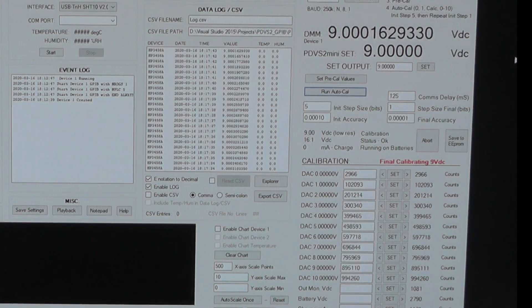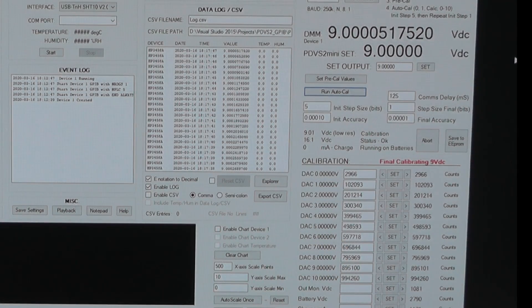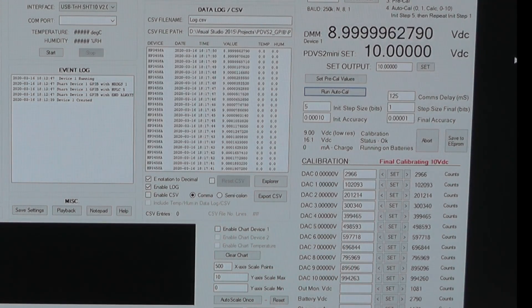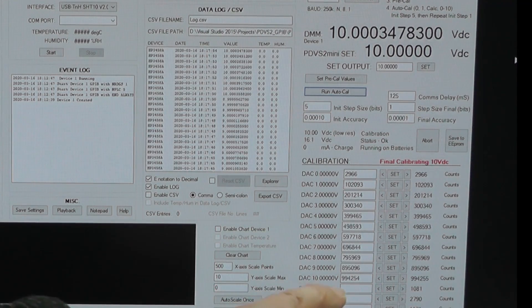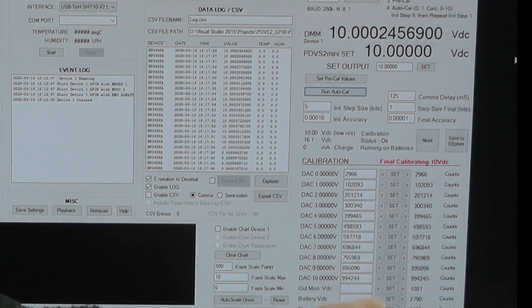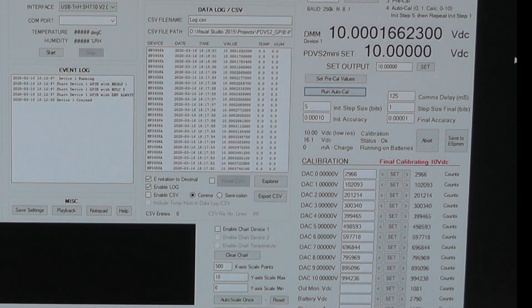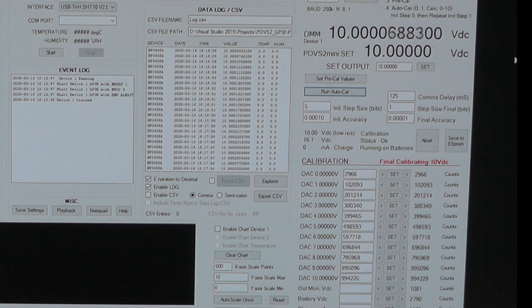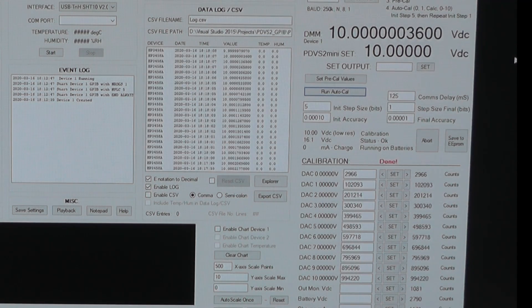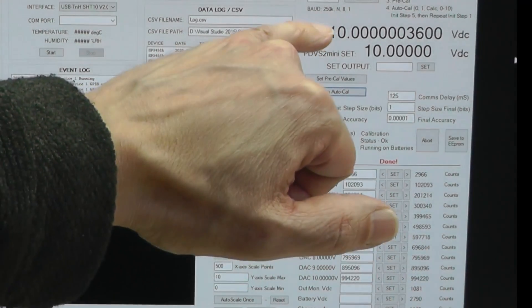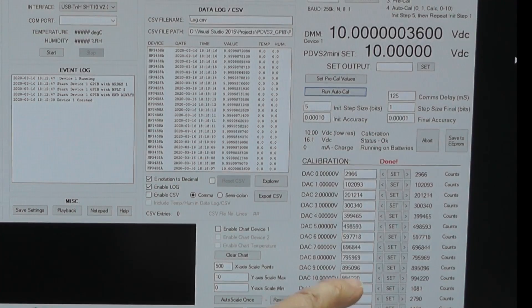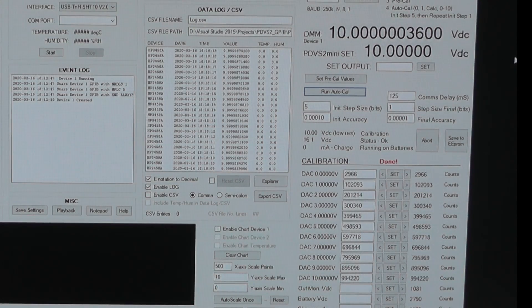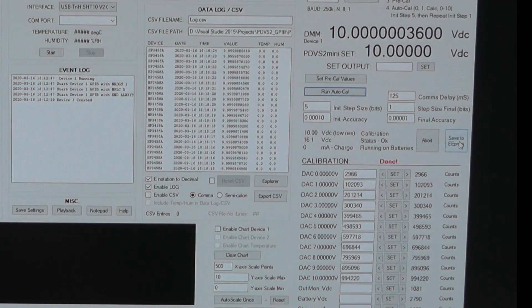You know this calibration - these are big numbers because it's a 20-bit DAC so it's got over a million bits, hence the big numbers at the bottom - 994,000. We're on the 10 volt one now, we're getting pretty close. So sometimes it does roll over onto one million, sometimes most of the time it's just a little bit below. And there it is, it's finished, we're done. That was the final value of the calibration for 994,220 bits. So now I just need to save it to EEPROM, so I'll do that now.